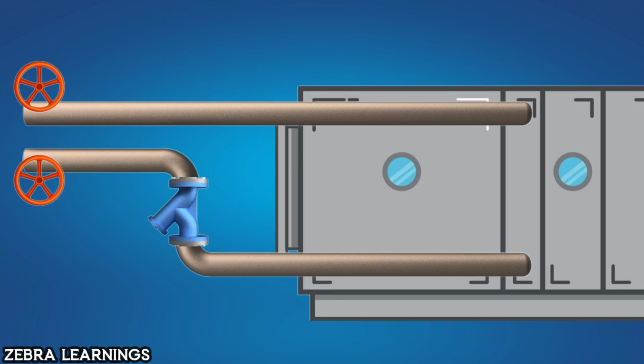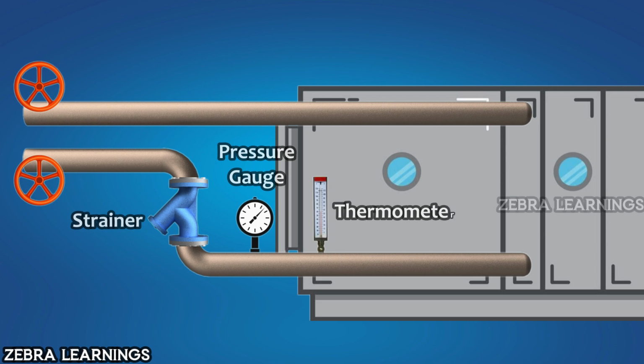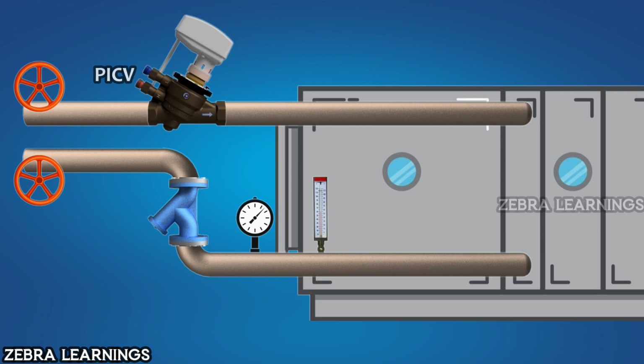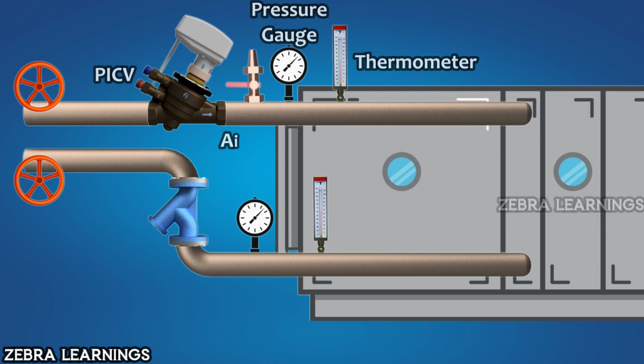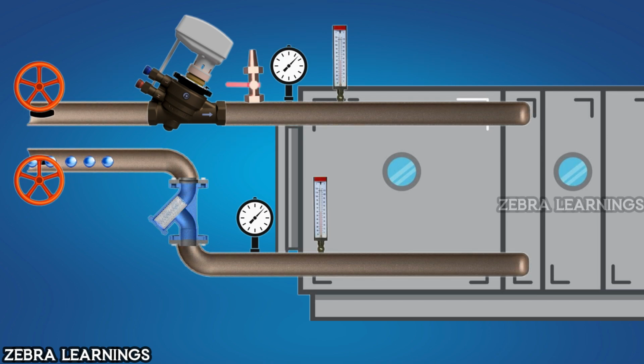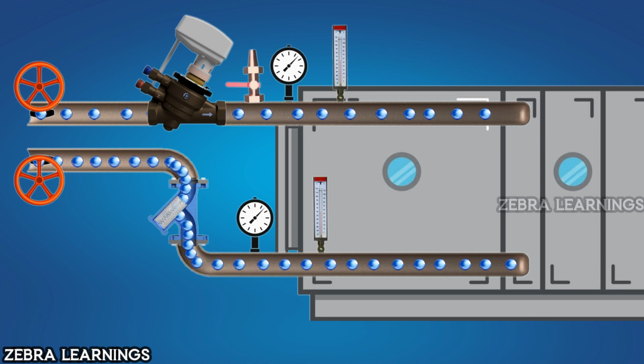The AHU pipeline will be like this. The supply line will be connected at the bottom of the AHU cooling coil, and the return line will be connected at the top. The supply line will have a strainer, pressure gauge, and thermometer installed, while the return line will have a PICV, pressure gauge, thermometer, and air vent installed. The water flowing through the supply line will be filtered through the strainer and then enter the AHU. After the AHU uses the cooling in this water, the water will flow back through the return line and return to the chiller. All the debris filtered from the water will be collected and stored in the strainer.